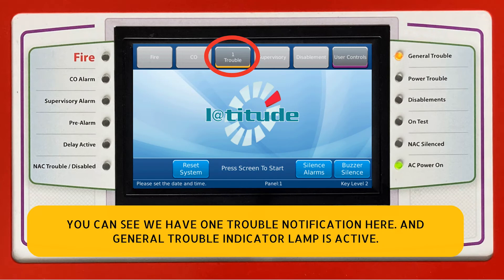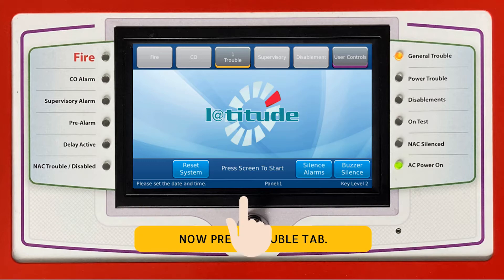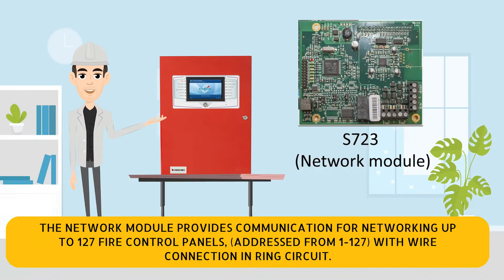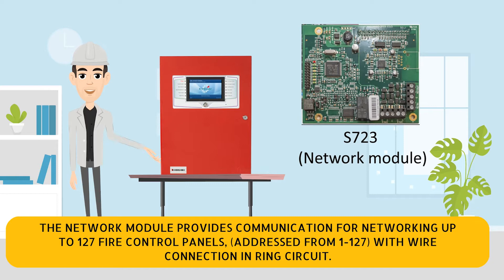You can see we have one trouble notification here and the general trouble indicator lamp is active. Press the trouble tab — the system has reported a network short circuit trouble. The network module provides communication for networking up to 127 fire control panels.